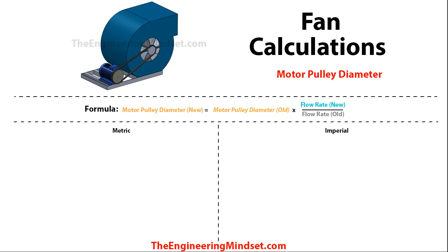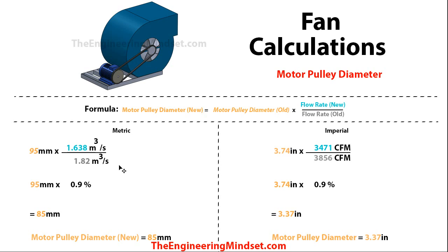Another way to do this — if we know there has been a change in the flow rate and we need to know what the change in diameter for the pulley will be on the motor — we can use this formula: the new pulley diameter is equal to the old motor pulley diameter multiplied by the new airflow rate divided by the old airflow rate. We know the old airflow rate and the diameter of the pulley, and this is the new airflow rate. Dropping these numbers in, we can see that the original pulley diameter multiplied by that ratio equals 85 millimeters, or 3.37 inches. That's the new motor pulley diameter.